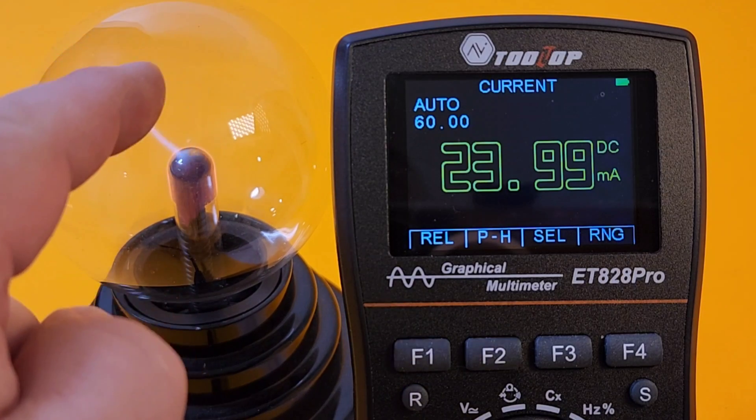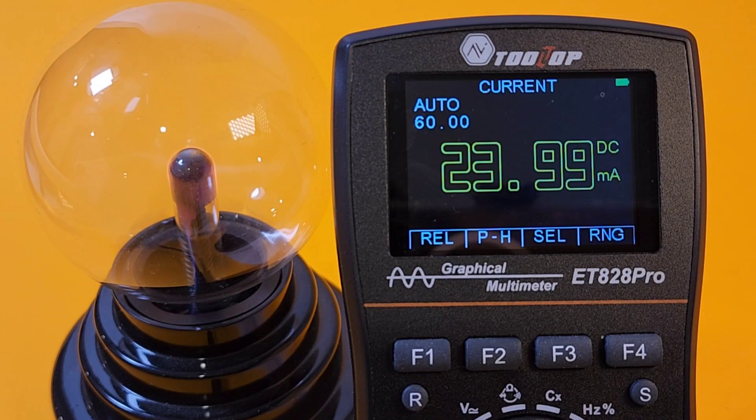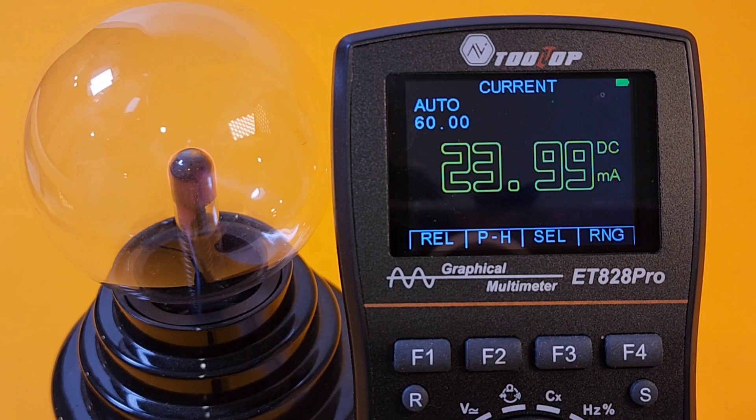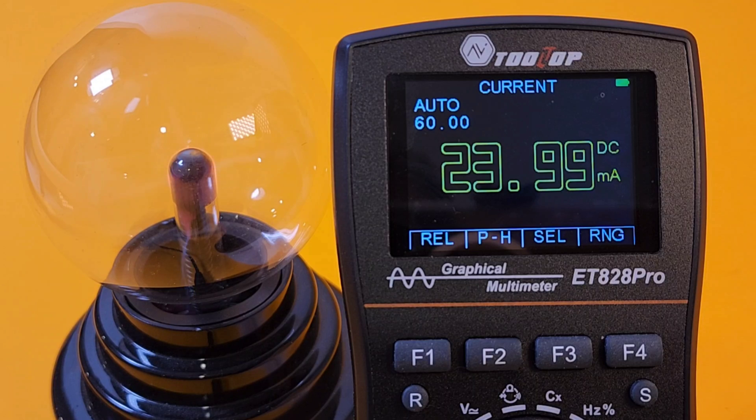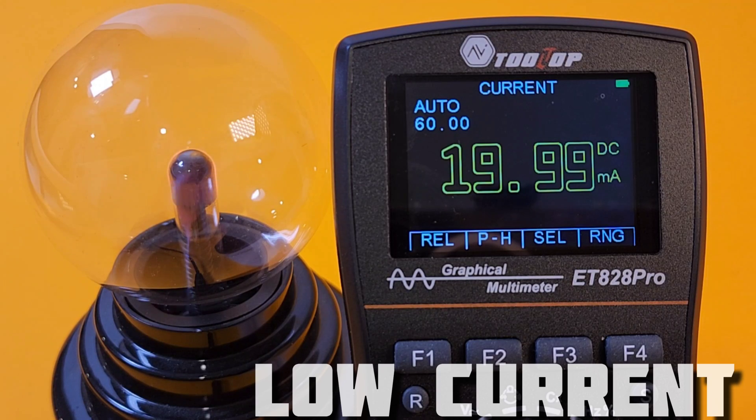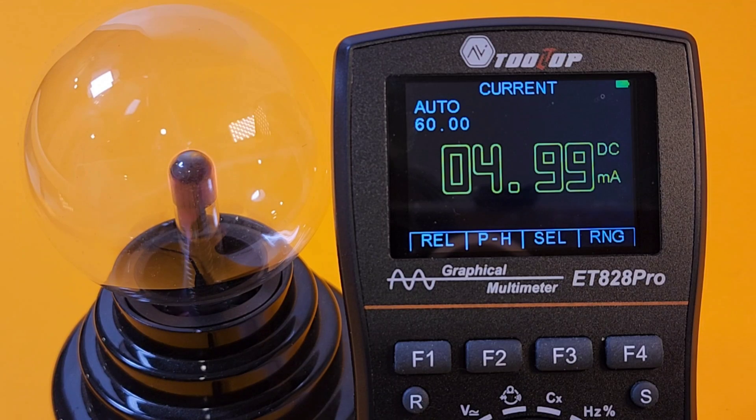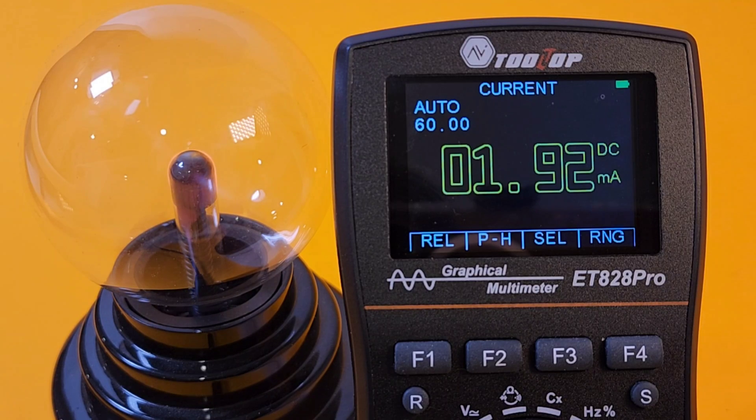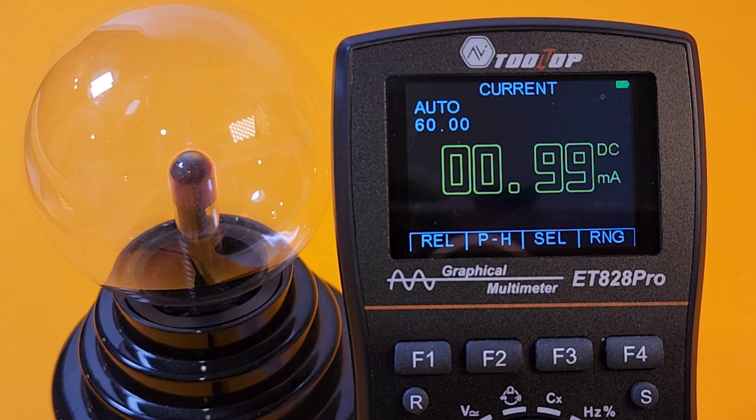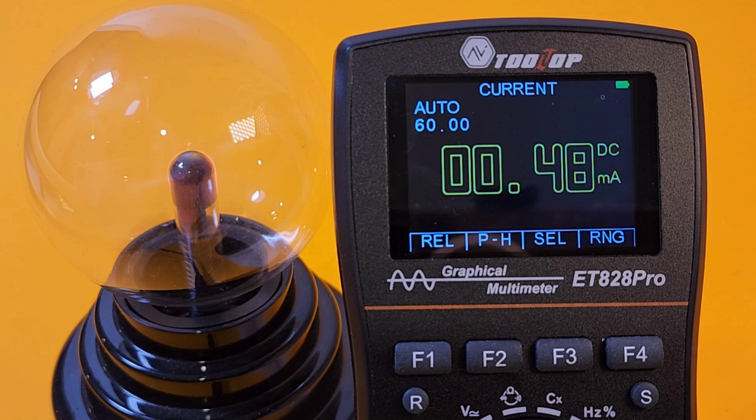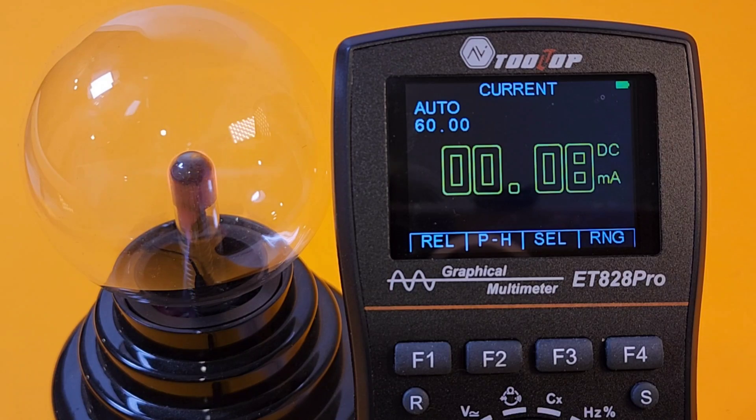I'm having too much fun here. All right. Now we're looking at milliamps. Sitting at 24 milliamps right now, coming in at 23.99. Hey, not too shabby. Let's bring it down. Sitting now at 20 milliamps spot on, coming in at 19.99. 10 milliamps. 9.99. 5 milliamps. 4.99. Just 0.1. Oh, wow. So close. And let's bring it all the way down to 1 milliamp. 0.99. Sitting at half a milliamp. 480 microamps. So you can tell in the low current spectrum, no problems whatsoever.